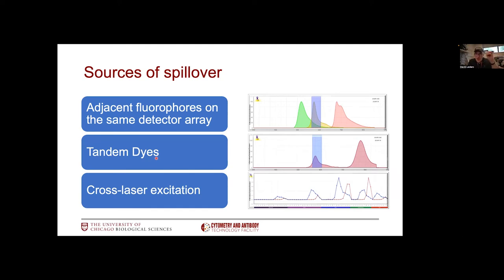A bit of photons is sent by the first molecule, the donor molecule in the tandem dye, and might end up in the wrong detector. By the same token, the second molecule might also be excited by a laser beam and spill in the wrong channel, generating the same false positive. Lastly, we have a case where some fluorophores get excited by multiple laser beams and shoot photons all over the place, possibly in detectors used for other markers in your assay. An example would be PerCP-Cy5.5, which bleeds all over the place. This is why we recommend using that fluorophore very late in the game.